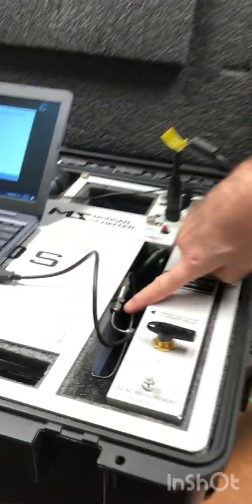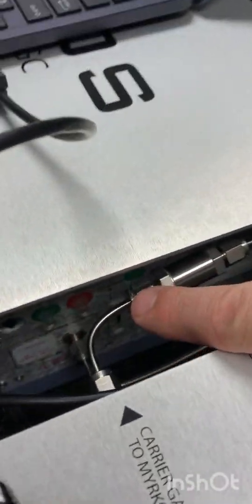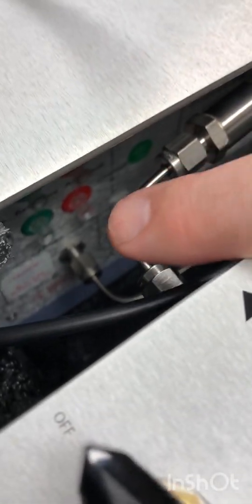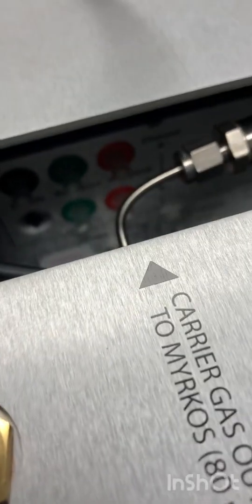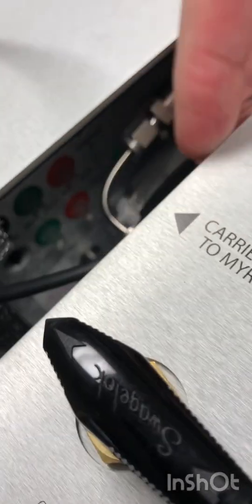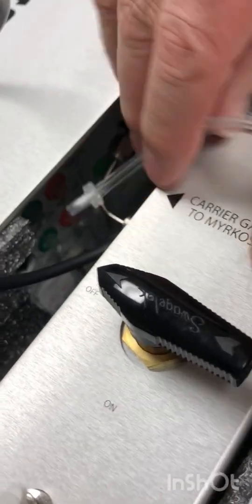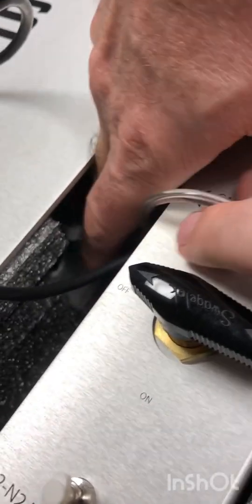In the back of the Myrkos there are four red and green outlets and a black one. For each of them you connect the bubble trap — it's a little bit tight so you have to have small fingers and patience. You put one bubble trap connection here like that, and you put the other extremity in a vial of water.